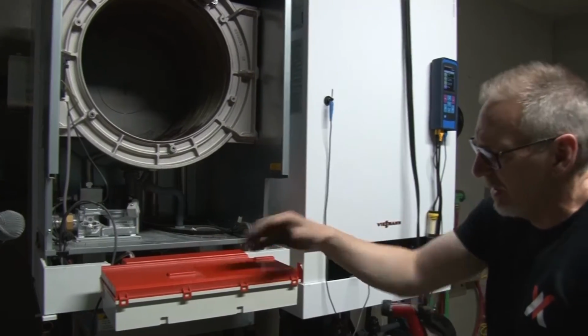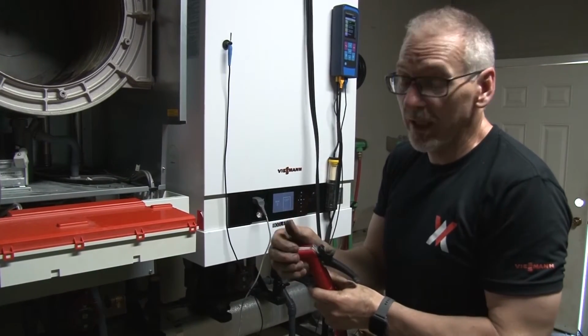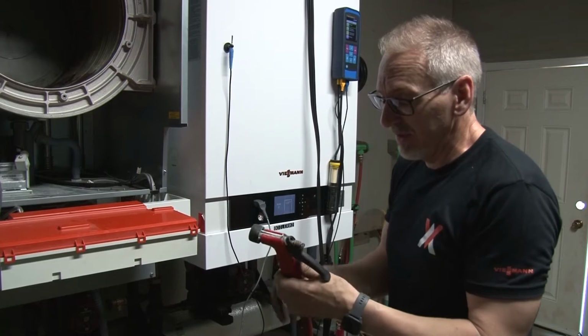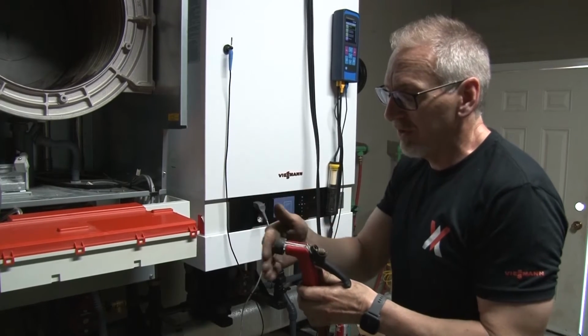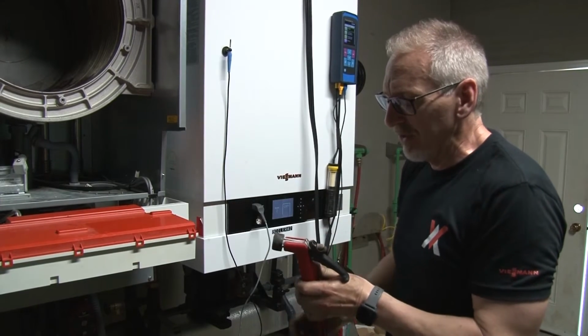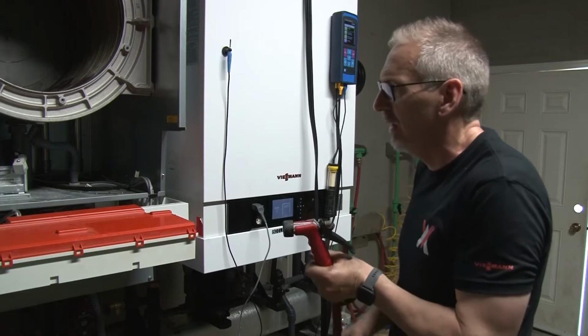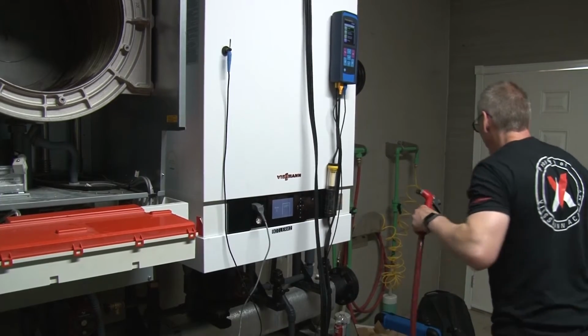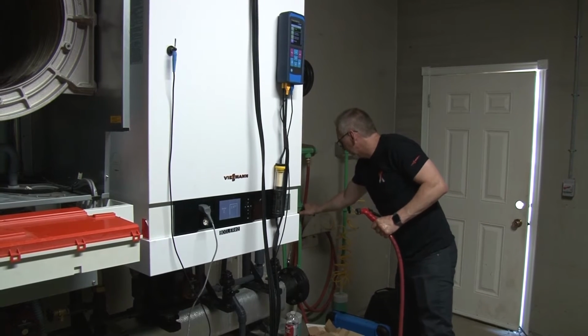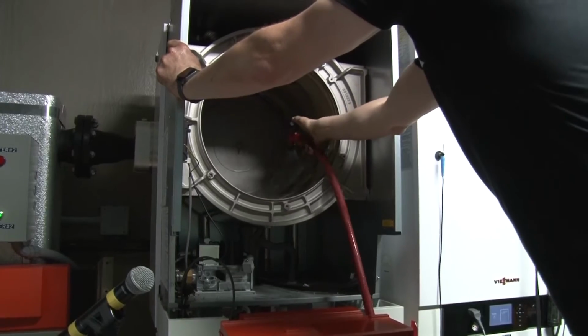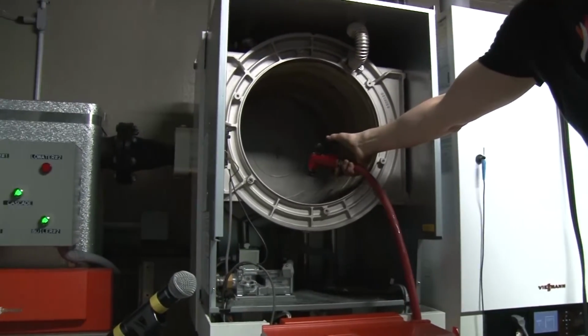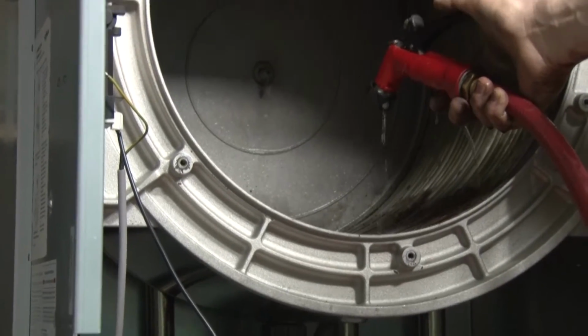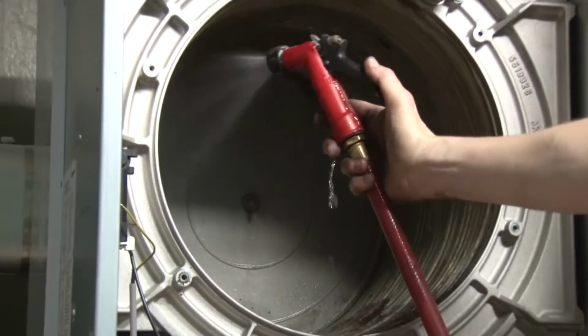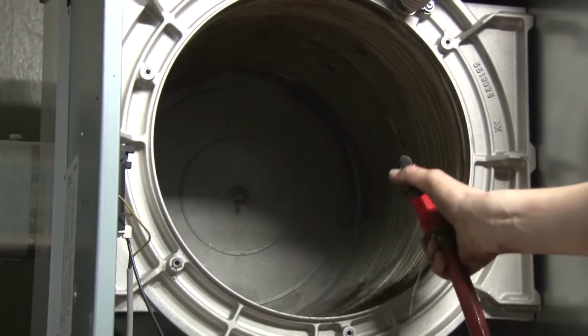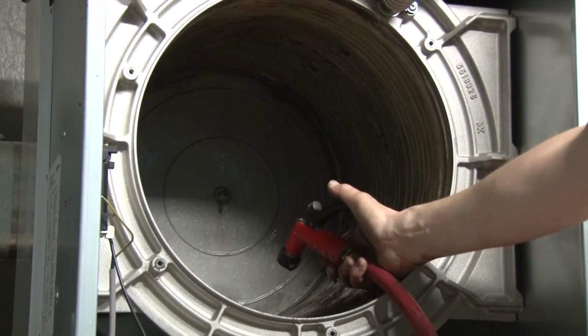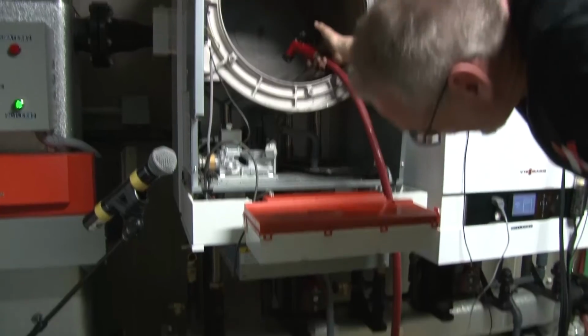Again, we've got electronics here. You want to have really good control of the water flow as we clean this boiler. Some guys will use, instead of a nozzle like this, a piece of 3/8 or 1/2 inch copper tubing. They'll flatten the end of it so they get a nice little distribution nozzle on it, and a little needle valve or something like that, so they can really control their flow. We'll work with what we have here. We used it yesterday quite effectively. Now, see how the water's kind of moving ahead a bit? I know some of these gaps are still kind of plugged. That should flush out fairly quickly. I want to get all of that chemical washed off the surface, being careful of where that water's going. Checking down on the P-trap here.